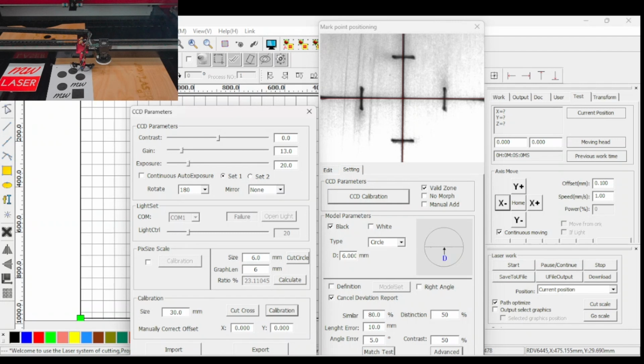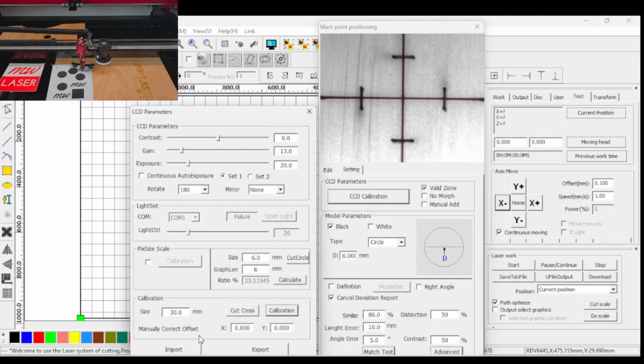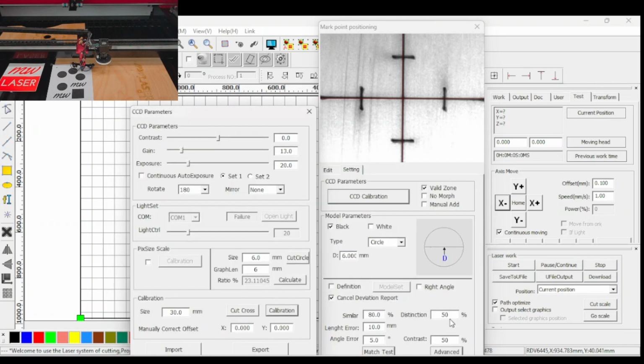Now, it's a very good idea to export your calibration files so that if you do change computers or if you need to reload the software, you can just import the calibration file without the need to redo your calibration every time. So we're just going to call this MW Laser 1610 and then whatever date or time or whichever machine that it's attached to. Save that file. So next time if you were to load the calibration and the calibration was out, we could import that calibration file and we know that that is now correct.